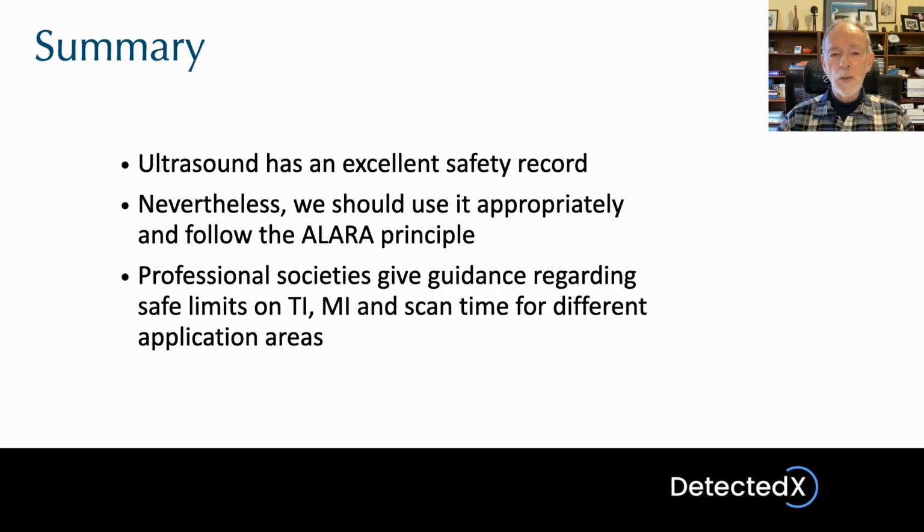Professional organisations around the world give you guidance regarding the safe limits for the thermal index and the mechanical index and the appropriate scan times for different application areas. And there are other principles, such as the one I've just discussed, about scanning patients only when medically indicated. So this basically is the framework for the safe use of ultrasound.